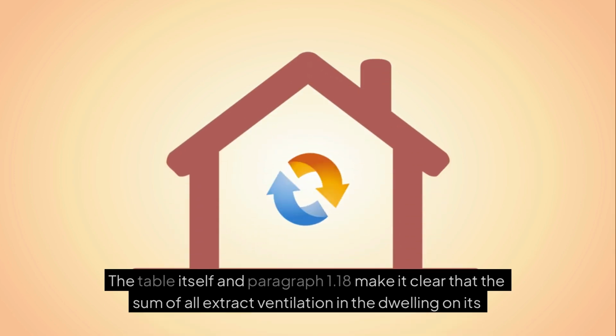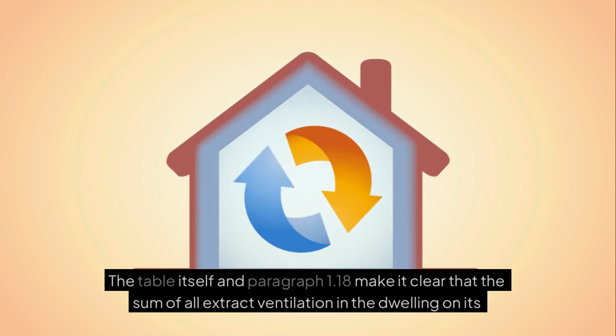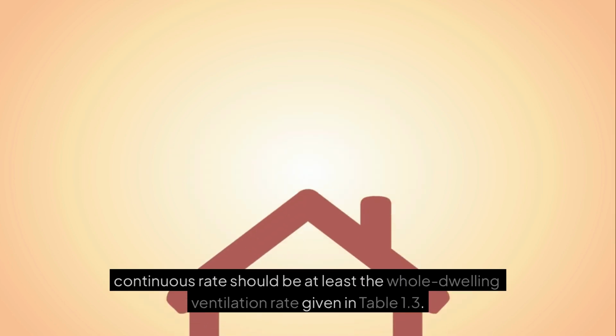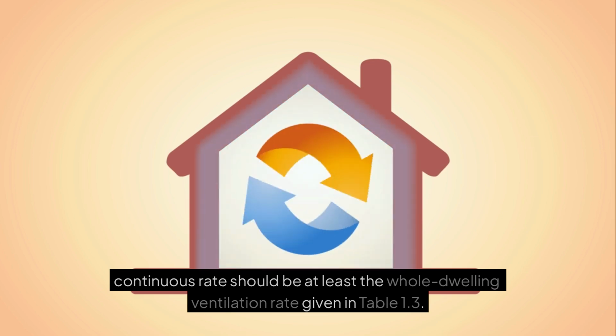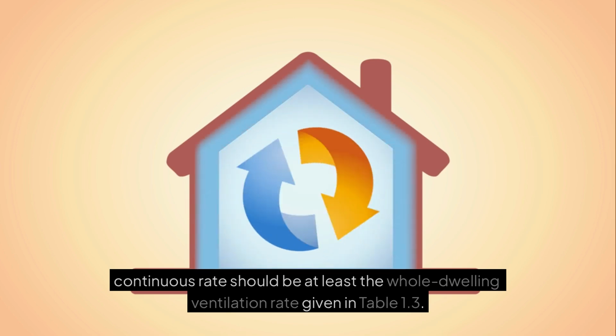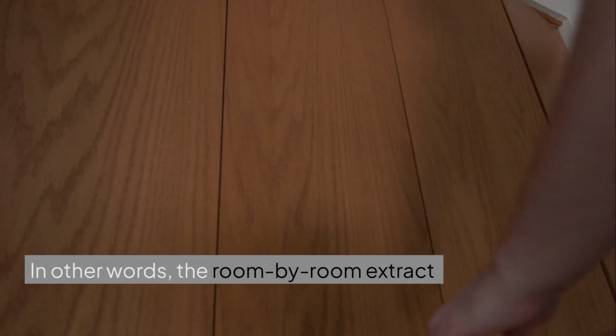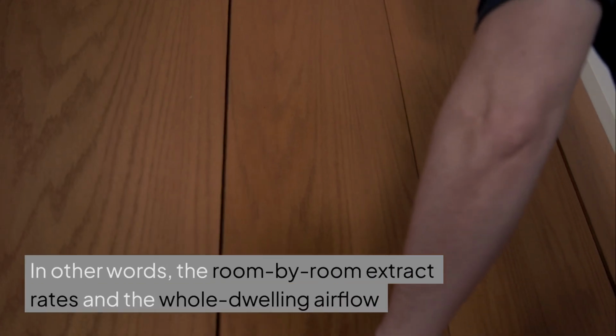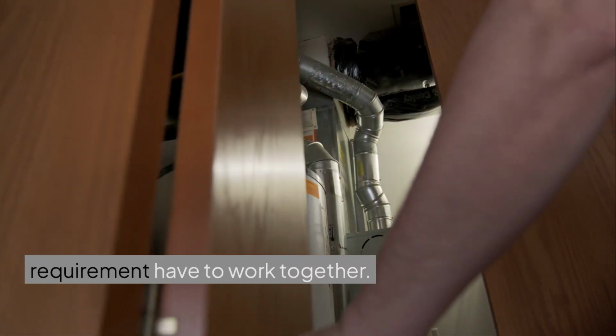The table itself and paragraph 1.18 make it clear that the sum of all extract ventilation in the dwelling on its continuous rate should be at least the whole dwelling ventilation rate, given in table 1.3. In other words, the room-by-room extract rates and the whole dwelling airflow requirement have to work together. That is a really important mindset point.